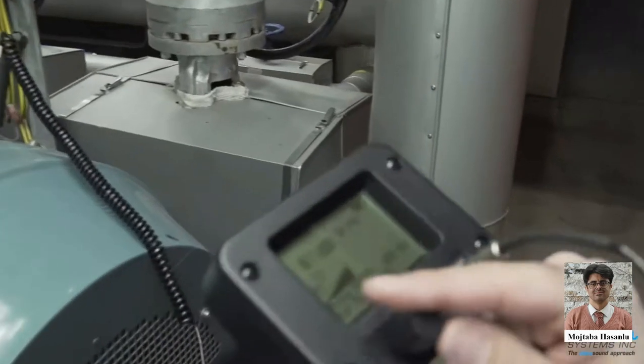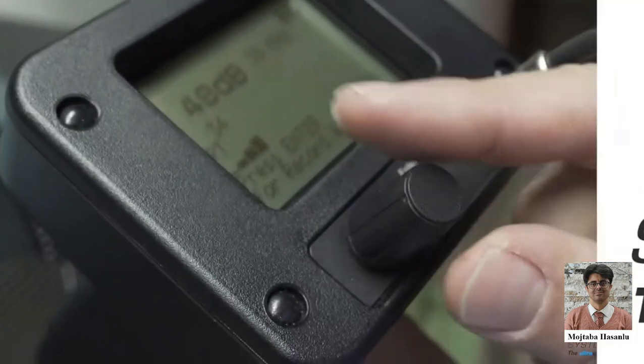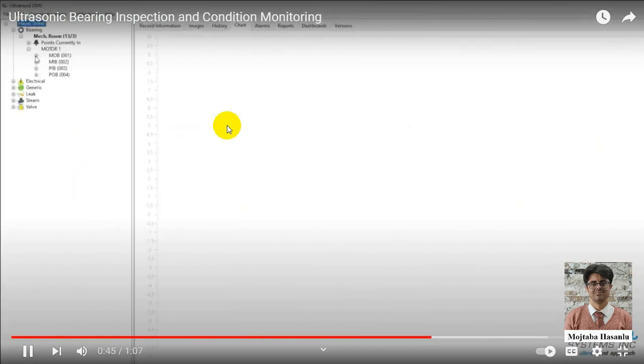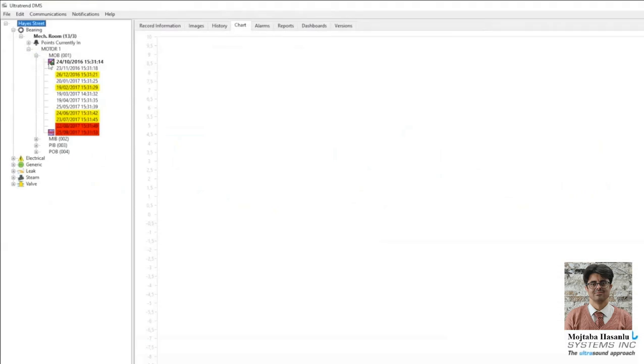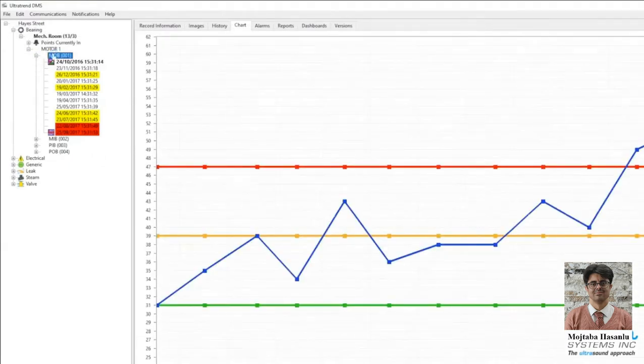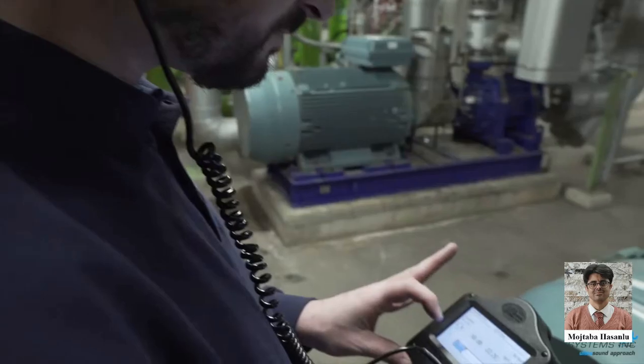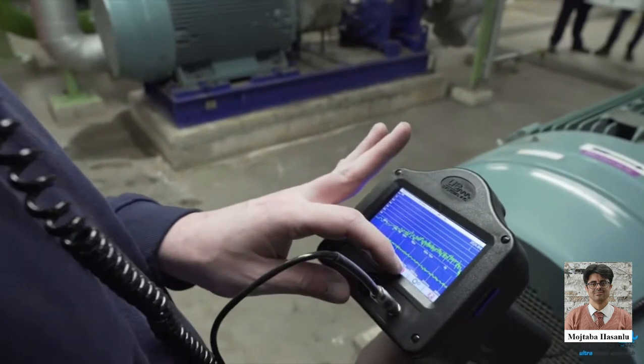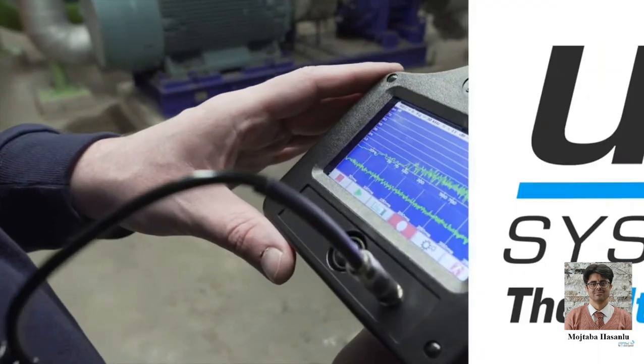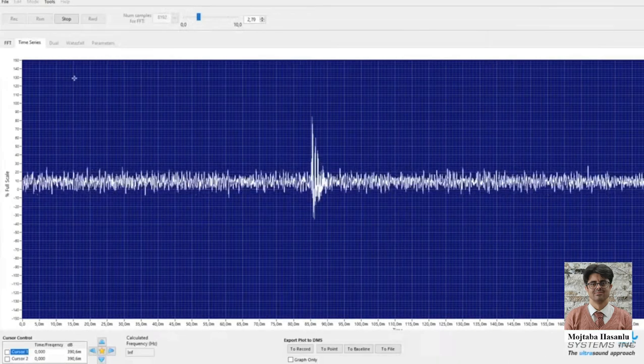Create a route in the DMS software with the baseline decibel values. Load that route onto the instrument and start your inspection. Compare your reading to the baseline to verify the condition of the bearing. For more advanced diagnostic, make a sound recording and analyze the sound spectrum using the Spectralizer software.